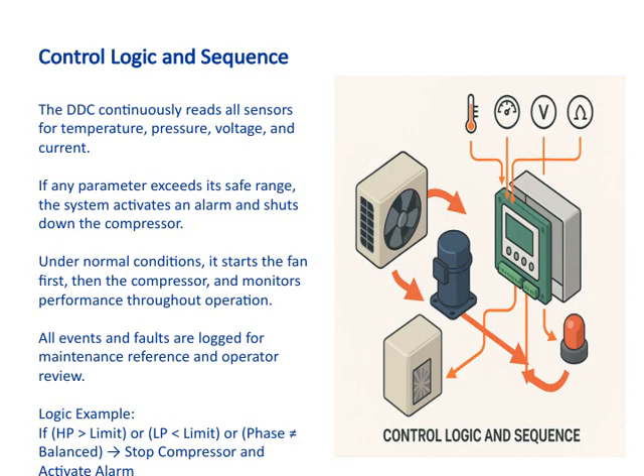On this slide, we're looking at the control logic and sequence that keeps our system safe and efficient. The DDC, or Digital Device Controller, continuously monitors all the sensors, so that's temperature, pressure, voltage, and current. It's always checking these parameters in real time to ensure everything stays within safe limits. If any of these parameters go beyond their safe range, the system responds immediately by activating an alarm to alert operators and shutting down the compressor to prevent damage or failure. This quick response is crucial for protecting the equipment.